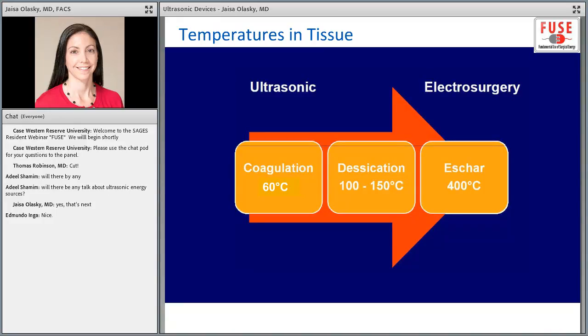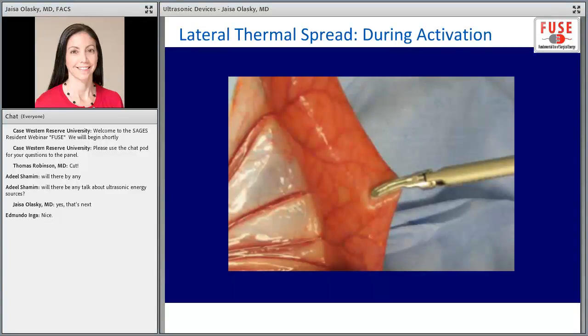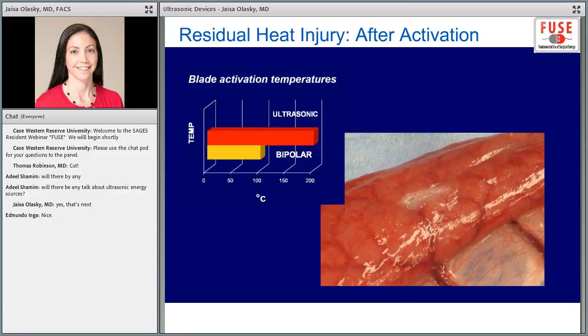So this slide just depicts what I mentioned before, that with the ultrasonic devices, you can have the tissue effects that you desire at a lower temperature. Here I'm showing an example of the fact that with ultrasound devices, you actually have less lateral thermal spread during activation than you do with some of the other advanced energy devices. What you're seeing here is you could use an ultrasound device in order to create an enterotomy before you do a bowel anastomosis, or a gastrotomy, or any other reason where you would like to make a hole in the tissue, but you don't want to have this thermal spread laterally, which later on in a few days might necrose and cause a leak at your anastomosis. So the ultrasound energy devices are really good for that. One of the downsides to these ultrasound energy devices is the residual heat.